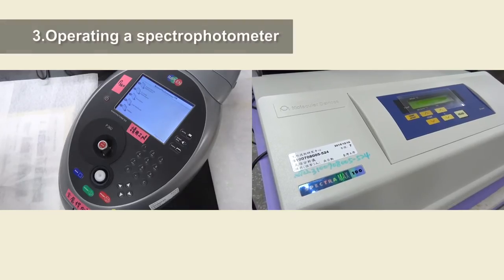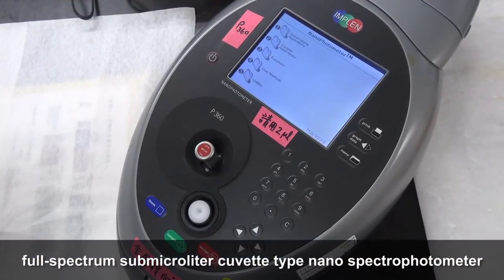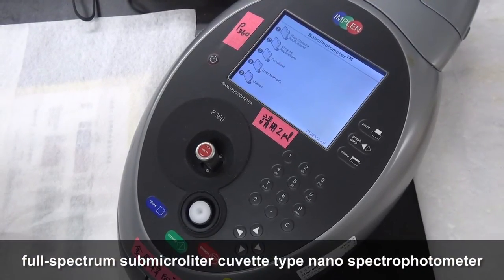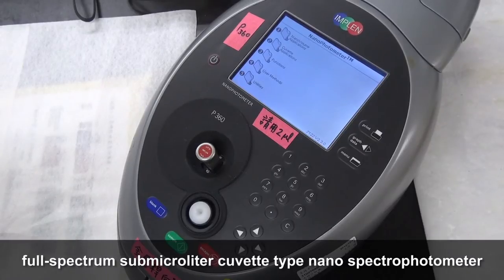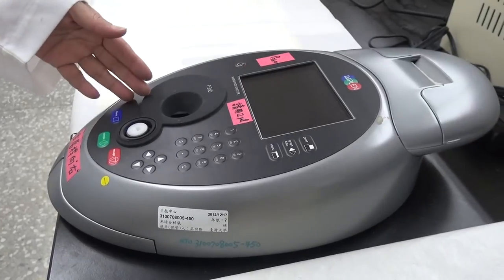3. Operating a spectrophotometer. A. Now we demonstrate how to operate a full-spectrum sub-microliter cuvette-type nano-spectrophotometer. 1. Remove the dust cover and make sure the cuvette holder is empty.